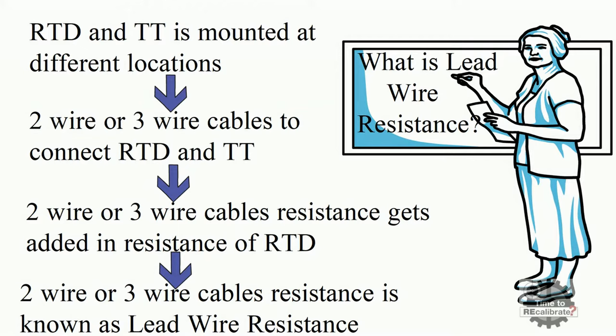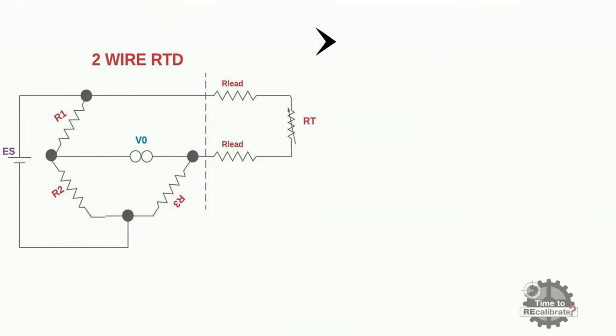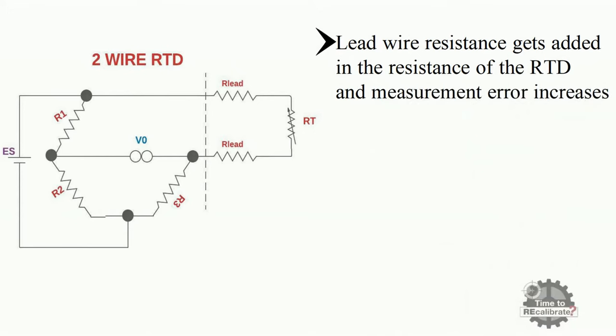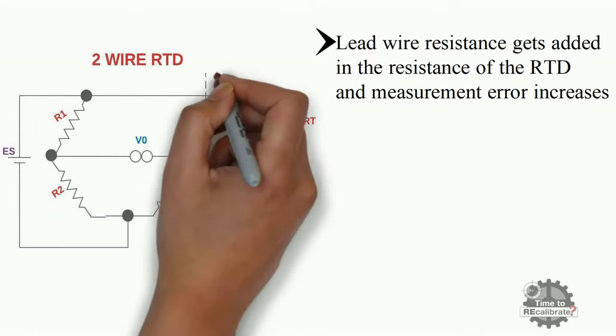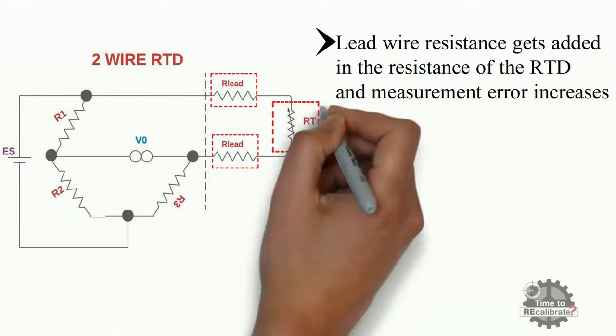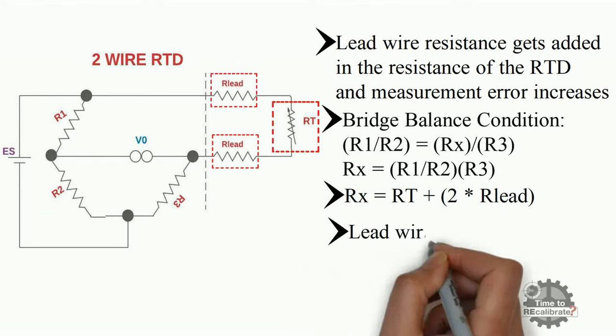These lead wires produce measurement error in temperature reading. As you can see from the circuit diagram of 2-wire RTD, lead wire resistance gets added to the resistance of the RTD, and because of the lead wire, the measurement error increases with increasing distance between the temperature transmitter and the RTD. In this circuit diagram, R1, R2, and R3 are Wheatstone bridge resistors; R-lead is the resistance of the lead wires; and RT is the resistance of the RTD. In the Wheatstone bridge balance equation, Rx is the sum of RT and 2 times the lead wire resistance, so the lead resistance clearly introduces error in measurement.